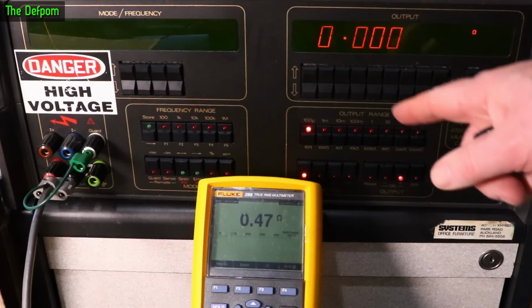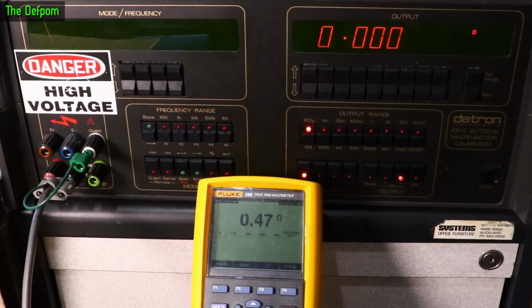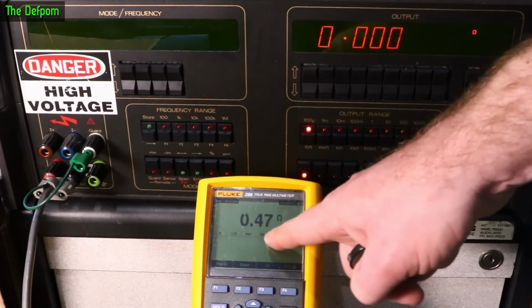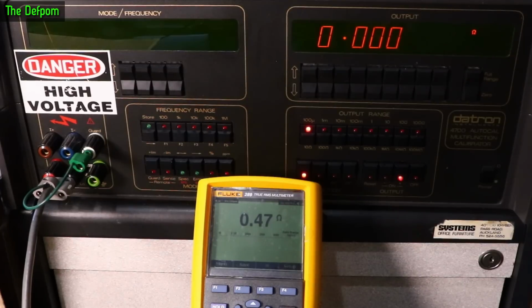So I've got it set up for 0 ohms right now. Output is turned on. You can see getting 0.47 ohms here, which is combined resistance. So obviously we've got this slight offset. If I short out with this little short here, directly across the meter input, you can see we're getting right down to basically 0 ohms, 0.01.